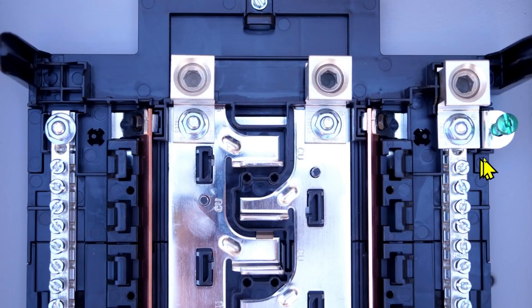So what happens in this load center when this bonding screw is screwed down? Well, this is your neutral lug right here. So your neutral feeder or your neutral overhead service conductor comes in and attaches right here.